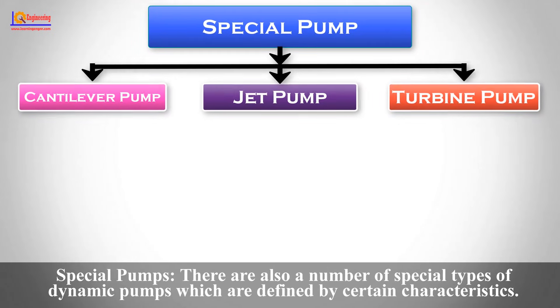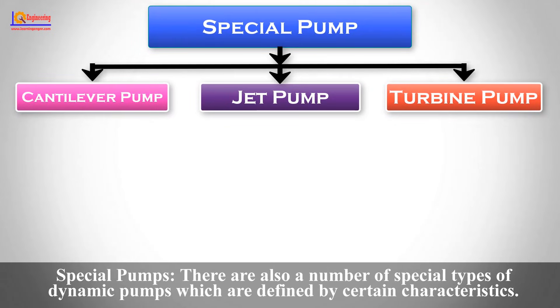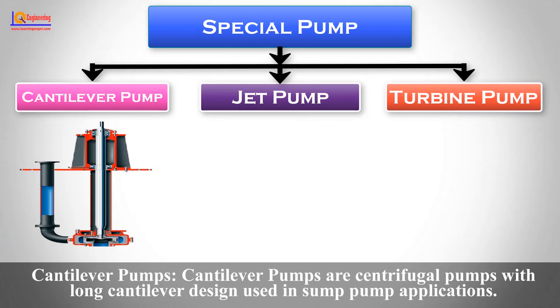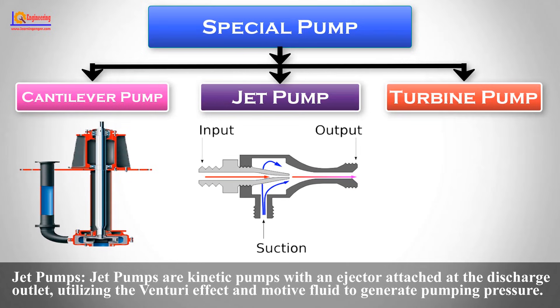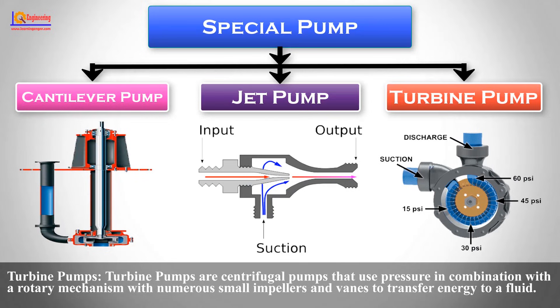There are also a number of special types of dynamic pumps defined by certain characteristics. Cantilever Pumps are centrifugal pumps with a long cantilever design used in sump pump applications. Jet Pumps are kinetic pumps with an ejector attached at the discharge outlet, utilizing the venturi effect and motive fluid to generate pumping pressure. Turbine Pumps are centrifugal pumps that use pressure in combination with a rotary mechanism with numerous small impellers and vanes to transfer energy to fluid.